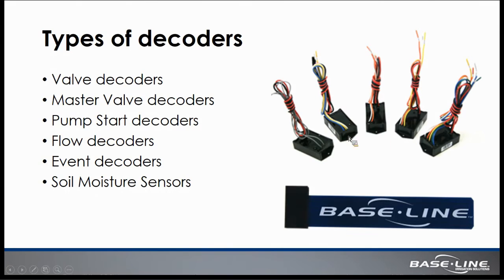The types of decoders vary, and they will vary by manufacturer as well. Everybody provides, of course, valve decoders that interface with the irrigation control valves. Master valve decoders that will interface with the master valve on the system, pump start decoders, flow decoders, event decoders, and smart sensors. As it relates to baseline, our soil moisture sensors are in fact a decoder device.